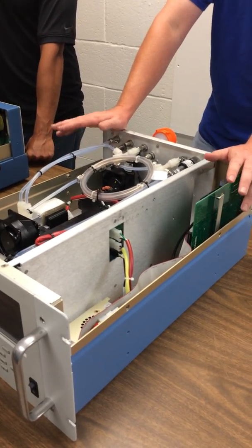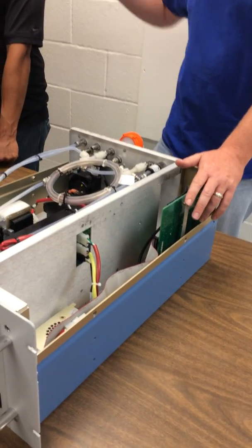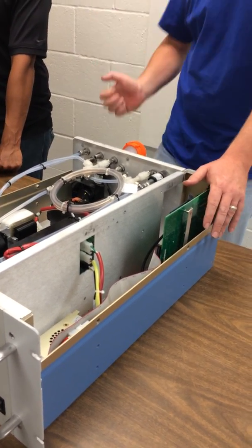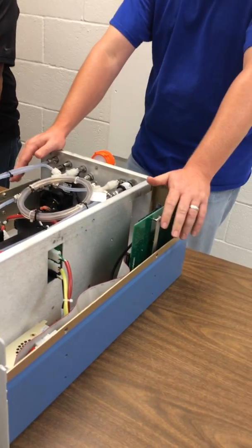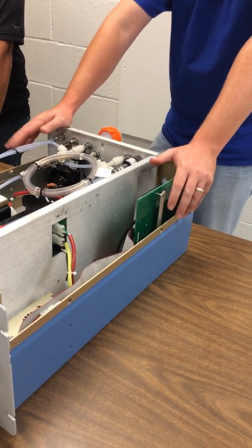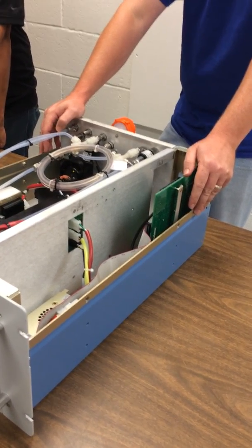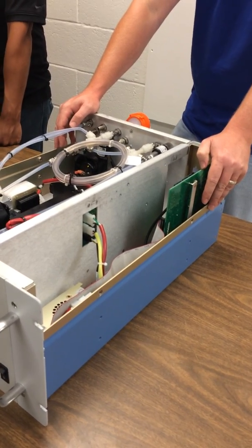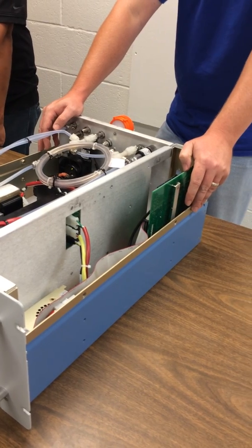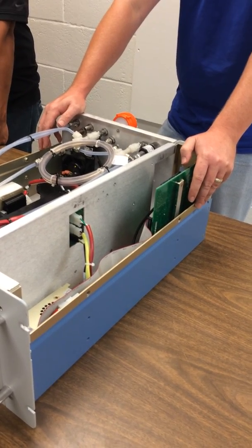We had to put a pump on the front end of it and push the air in so that we could pull enough air from outside and push it in so that the instrument never really thought it was much above Denver, even though we were at 30,000 feet. So that's the fun part of our job. We hardly ever leave instruments alone. We always get in and do something strange to them inside.